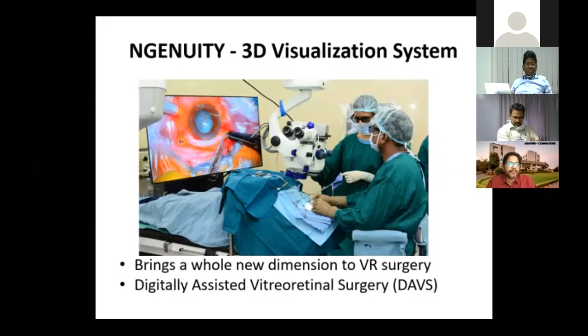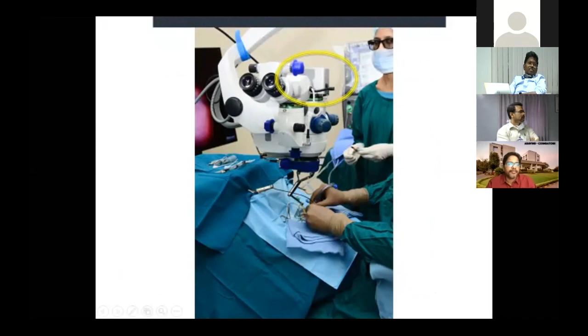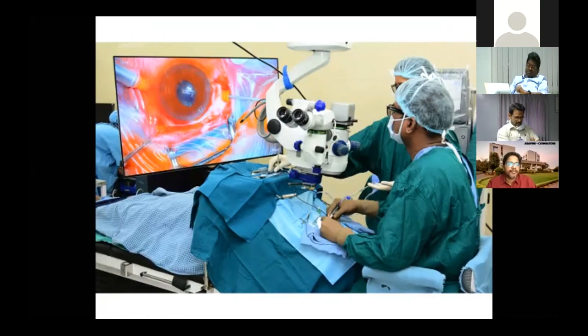This 3D visualization system has brought a new dimension to the entire VR surgery. What is happening here is that the eyepiece of the microscope is replaced by a high definition HDR camera. This is the hallmark of this system; the rest of things remain the same. The camera captures whatever is seen through the regular BIOM and resight system, and the image falls on a 55-inch three-dimensional television, kept roughly 90 to 120 centimeters away from the surgeon. Closer is bad, and farther away is also bad, so ideally it should be between 90 and 120 centimeters from the surgeon.